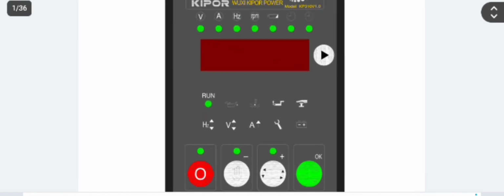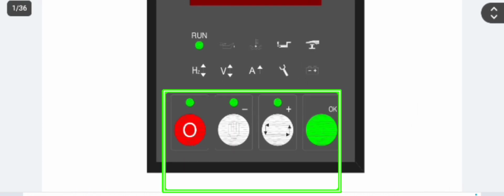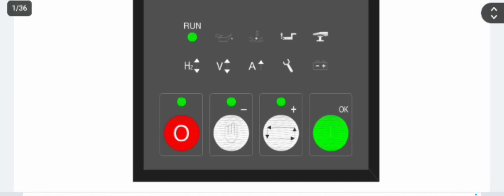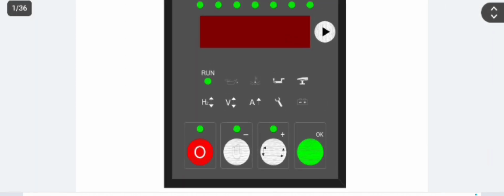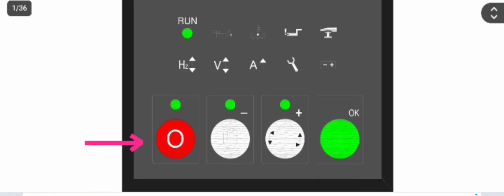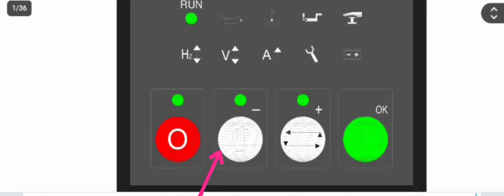So let's get started. First of all, a little review of the front display of this controller. As you can see here, on the downside we have four buttons: a red one, two white ones, and the last one is a green button. The red button is used for alarm reset or to stop the generator manually, and then the hand button, the minus button, and the positive button. The minus button is used to start the generator manually. First press the manual button, and then press the green button, and the generator will start manually.